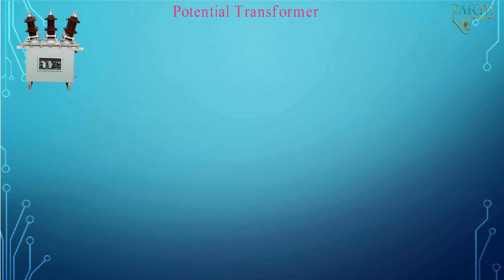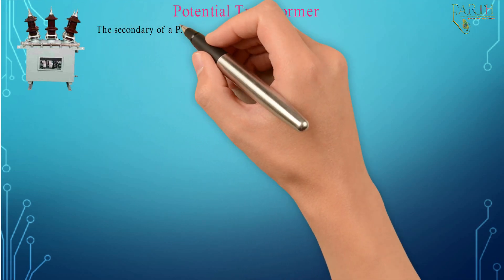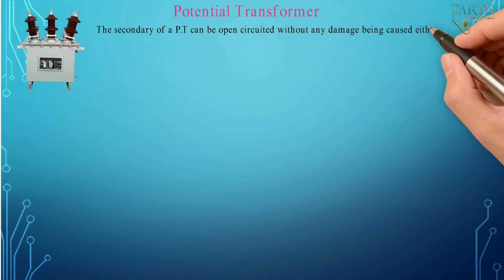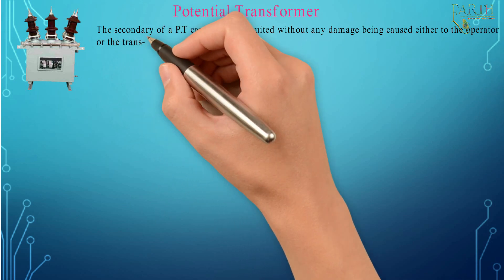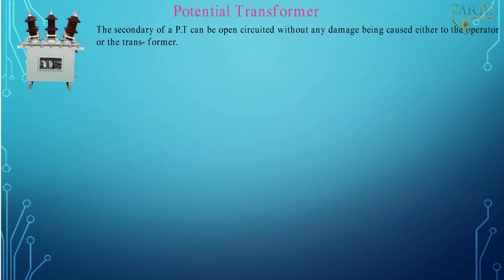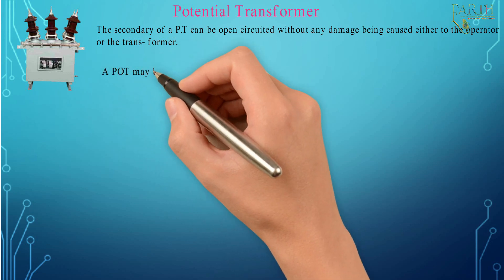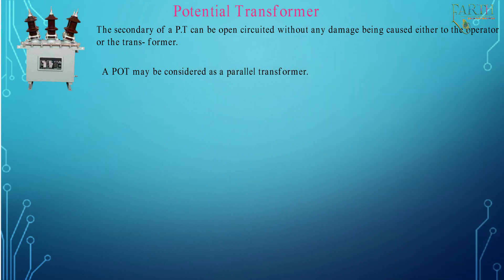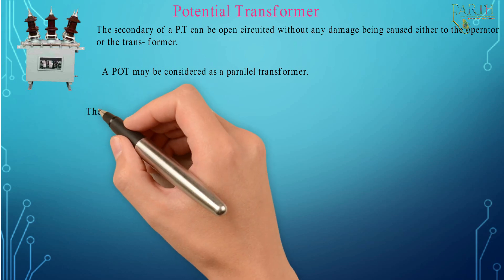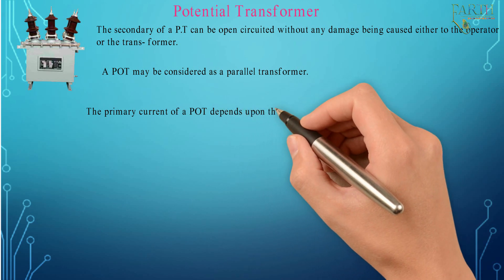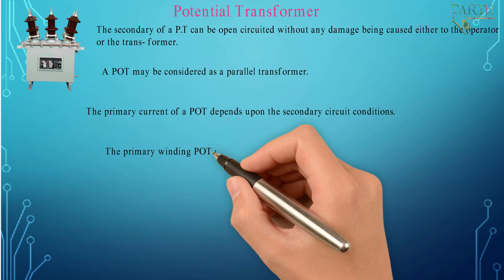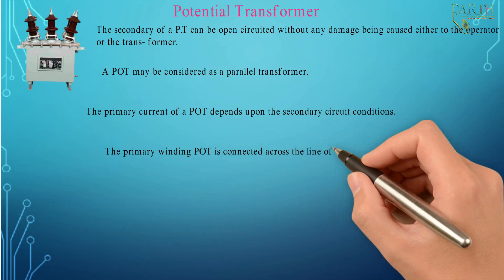Potential Transformer: The secondary of a PT can be open-circuited without any damage being caused either to the operator or the transformer. A PT may be considered as a parallel transformer. The primary winding of the PT is connected across the line of voltage to be measured.